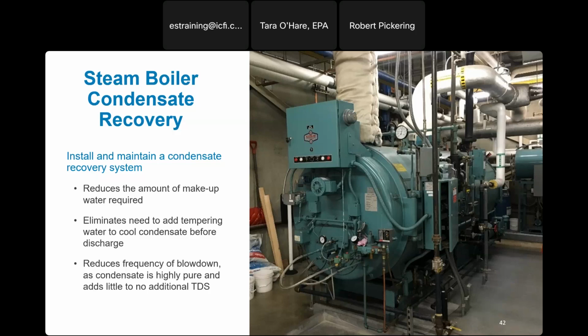Steam condensate recovery as a result has energy savings. Since the steam condensate is really hot, it requires less energy to reheat and produce steam again, and much less energy than incoming city water that is usually at, let's say, between 55 and 65 degrees.